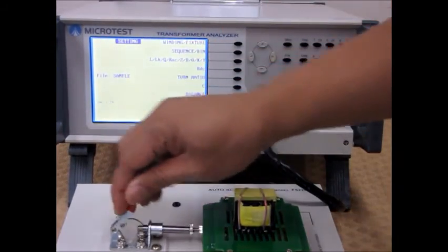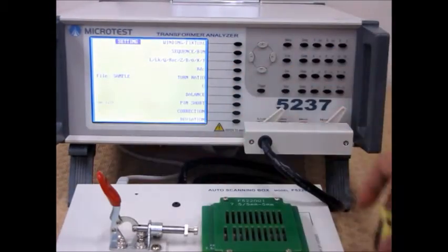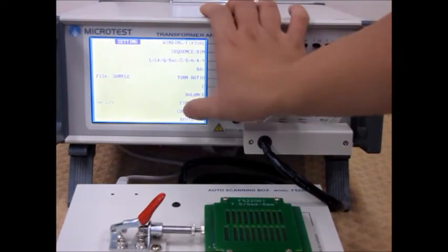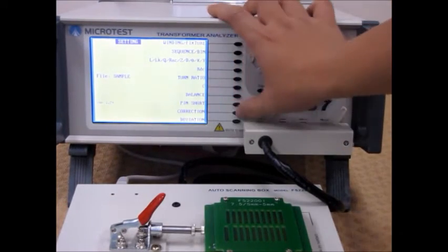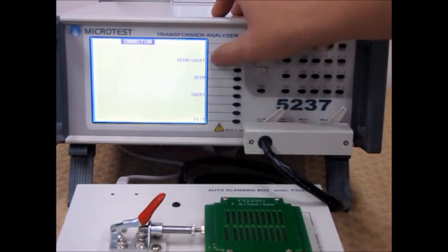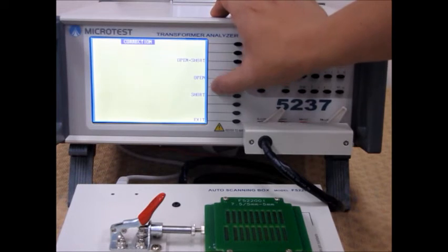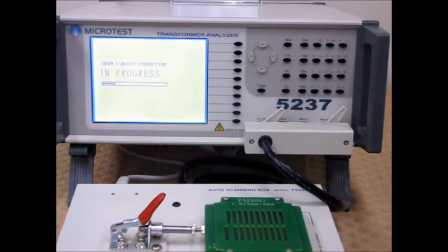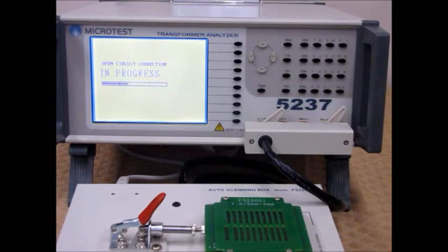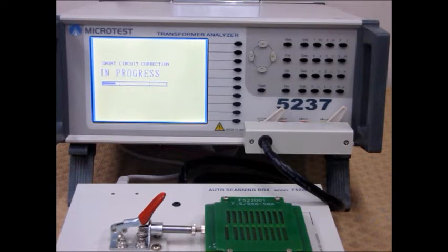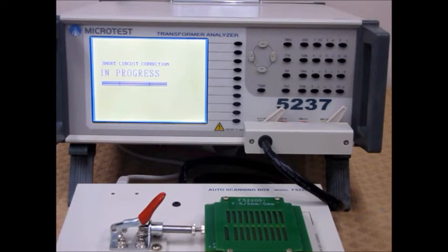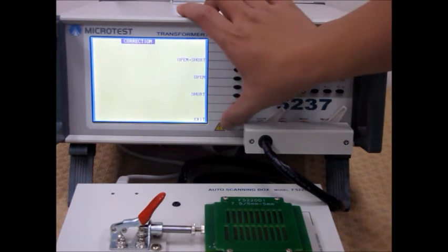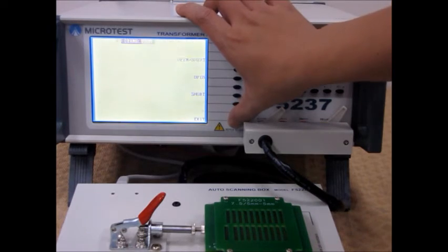Then you exit back to the main menu. Then you do the OS correction by taking out the transformer. Go to the correction menu, select open plus short, and the machine will perform the task. Then you exit.